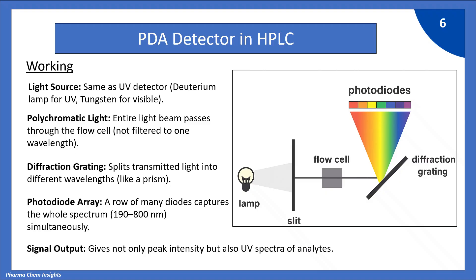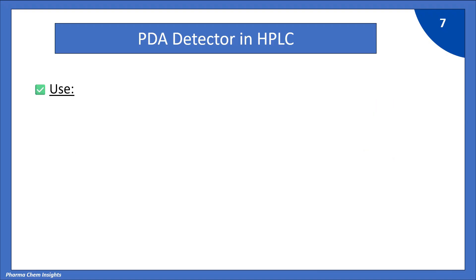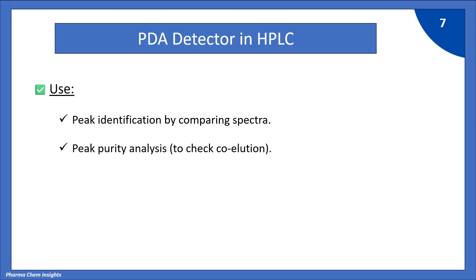The PDA detector also provides UV spectra of analytes. Its uses in HPLC include peak identification by comparing spectra, peak purity analysis to check for any co-eluting peaks, and structural characterization support.